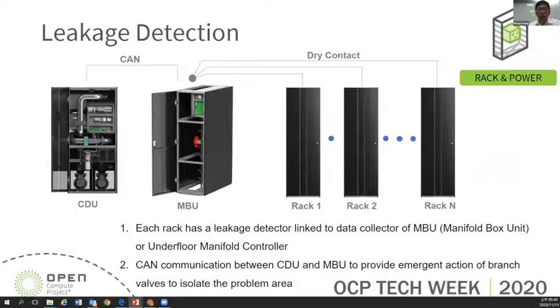The system comes with a water leakage sensor. If the sensor detects water leakage in one of the racks, the signal goes back to the controller in the manifold. The controller will shut off the water to the rack. This can prevent the water leakage from damaging the whole system.